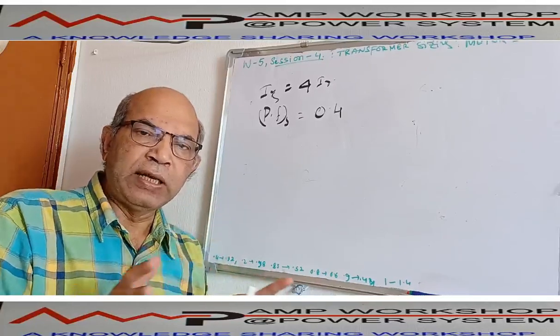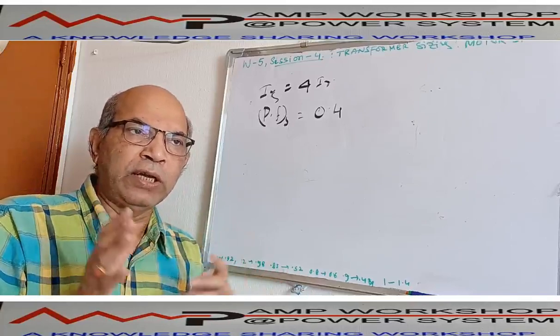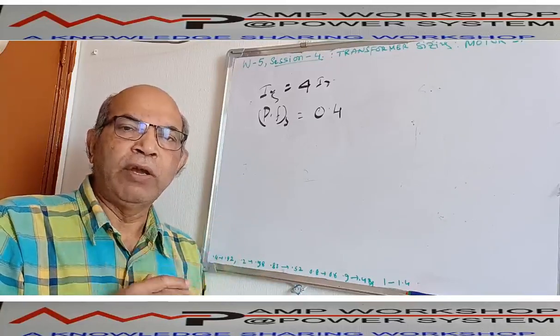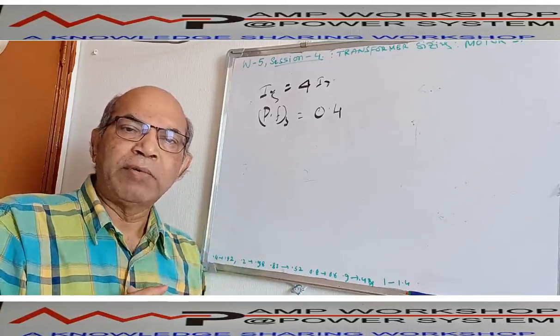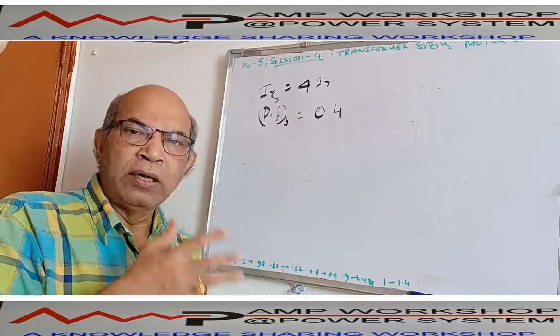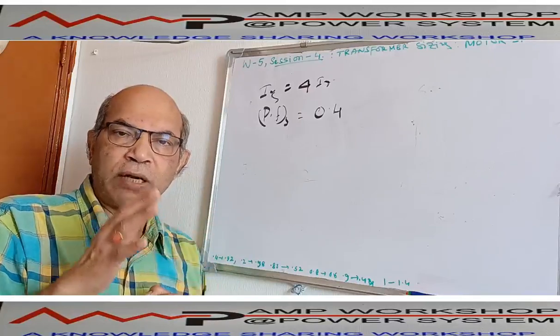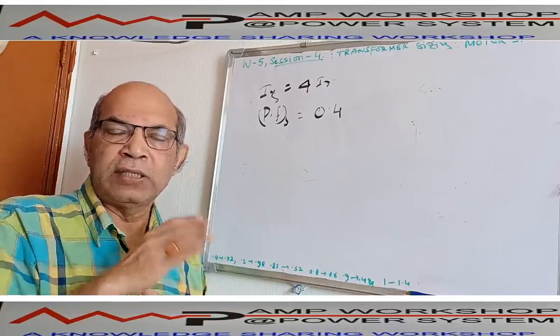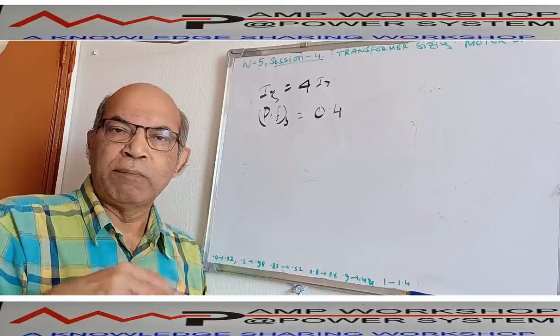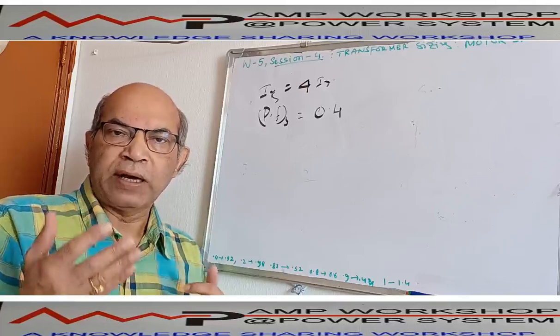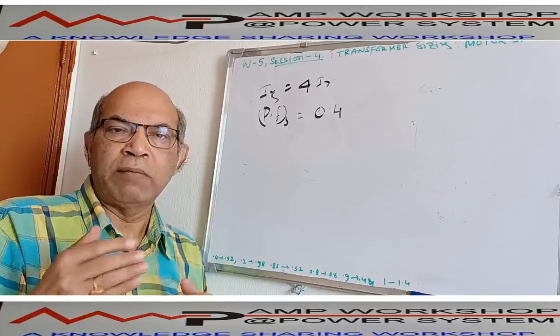That means the two scenarios are different. So we have to consider both of these scenarios when we size the transformer kVA. In case of normal load, which we discussed in sessions 2 and 3, we considered all loads as normal loads. There are no such types of loads in the process which can take different current at different times and have a different power factor.